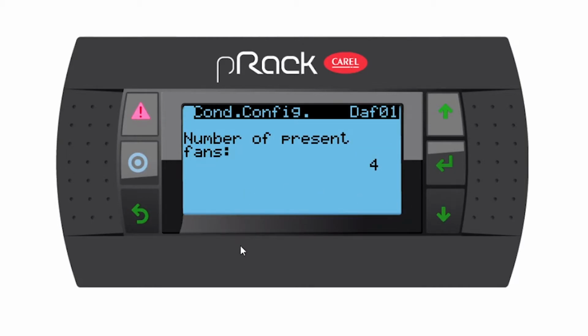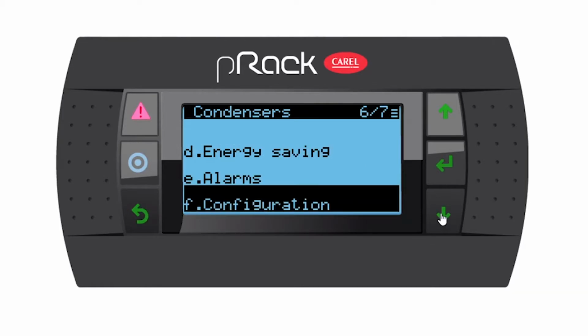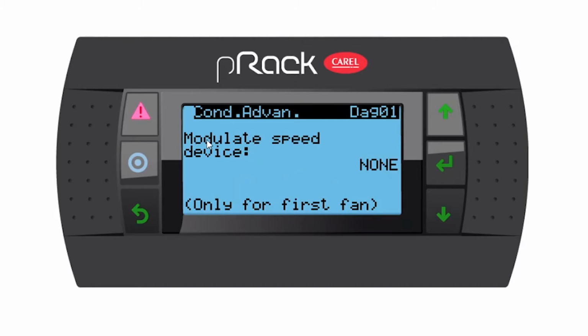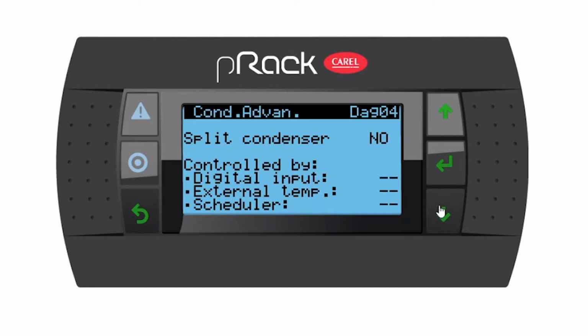If we go down, then we're back at the beginning. So let's escape from this menu and go to menu G, advanced, and enter. Modulate speed device is none because we only have the 4 on-off fans. No, we are not running a split condenser. So I'm going to leave this on no.